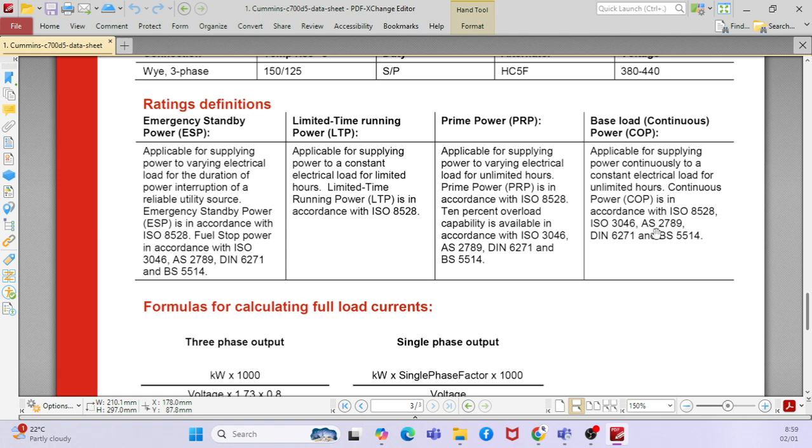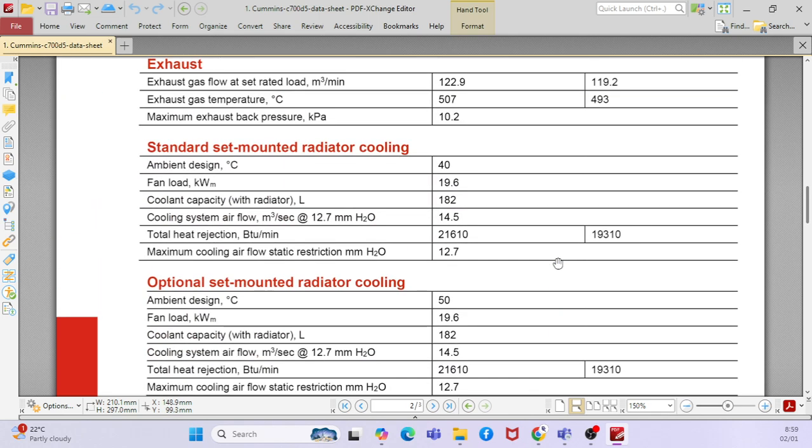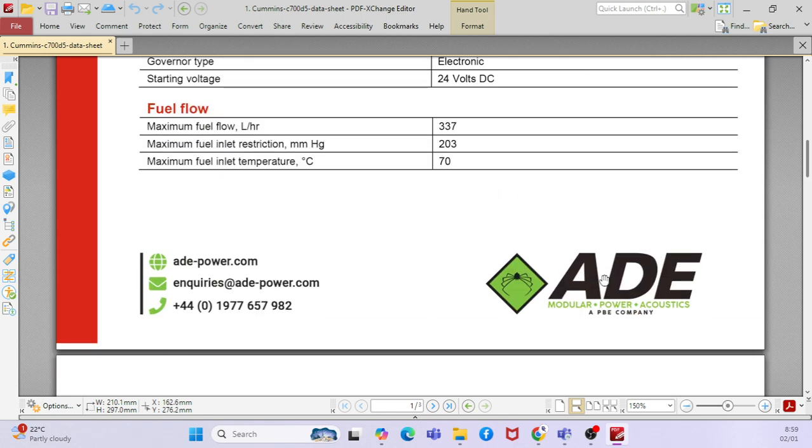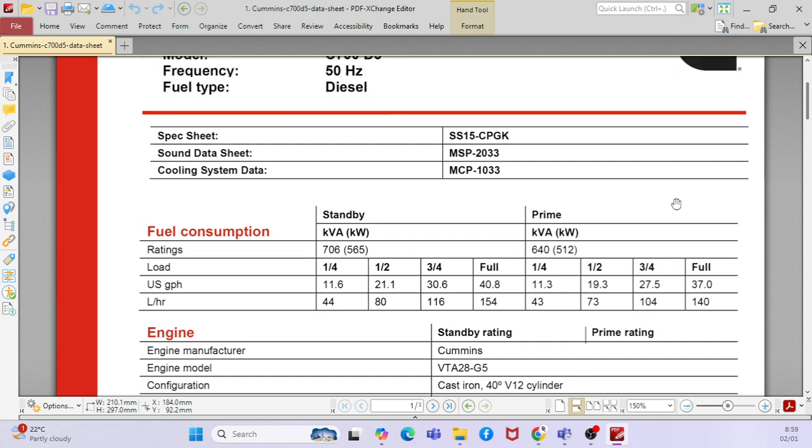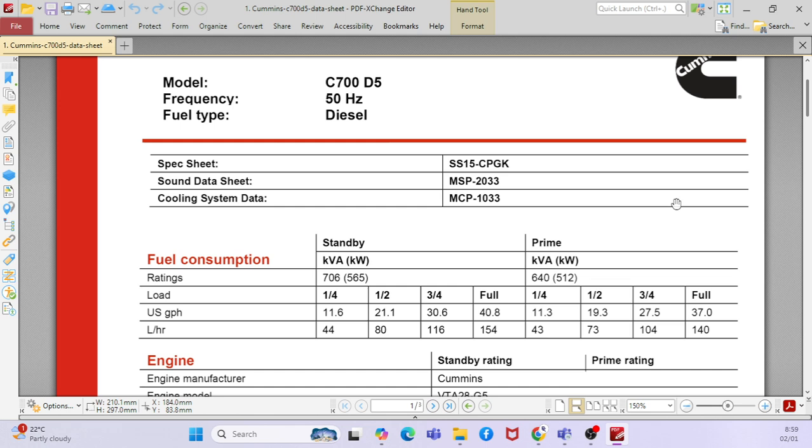Okay. So generally, when we go for generator selection and are communicating with the manufacturer, do we just have to say what type of project it is? Of course, yes. If it is a data center project, you will say this is the capacity, right? And if you are working on building projects, the capacity would be given by the electrical team only. But when you receive the selection from the electrical team, you should understand the difference between standby, prime, and continuous. Understood.